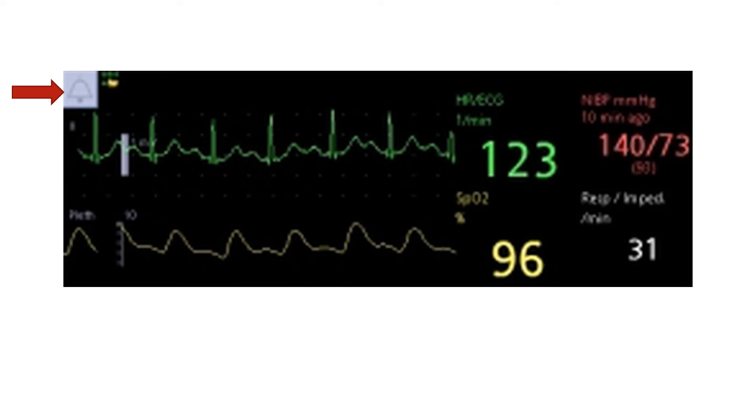Several alarms are triggered by poor signals on the ECG channel. This can be avoided by checking the 12-lead ECG and choosing monitor leads with the best QRS voltages. Poor electrode contact is another reason, which can be avoided by cleaning the contacts and changing the disposable patches once a day or if damaged.